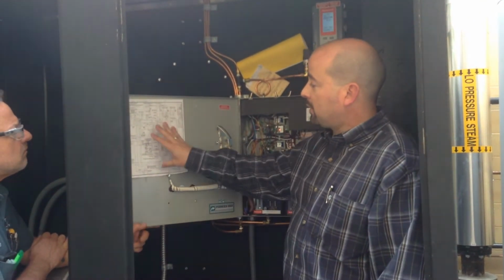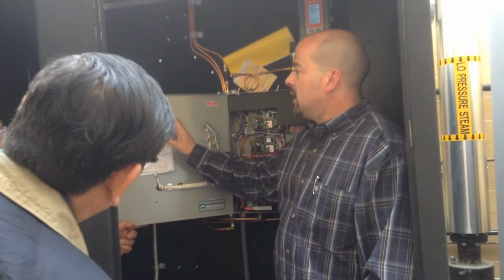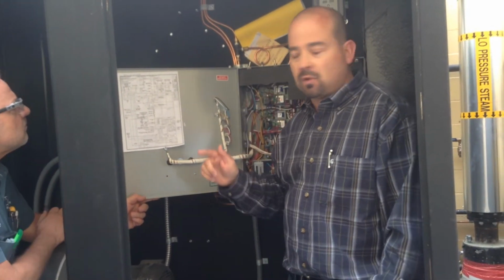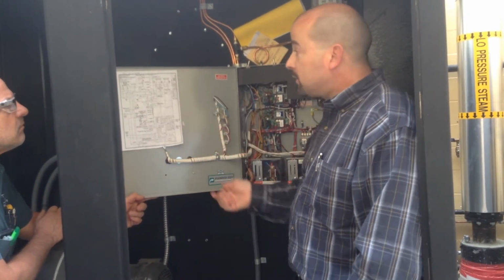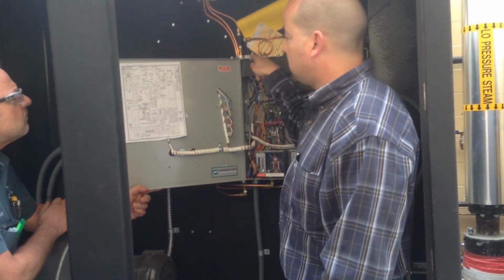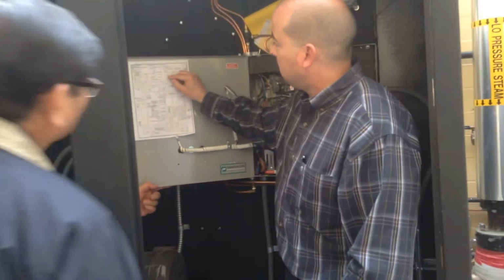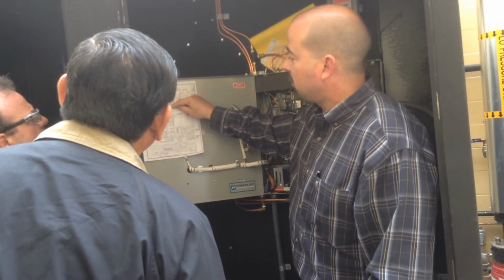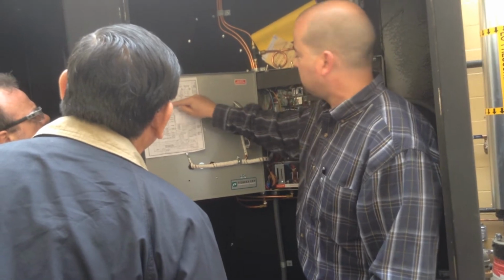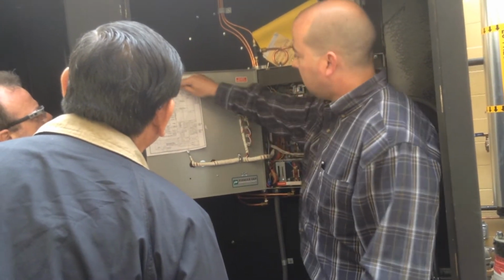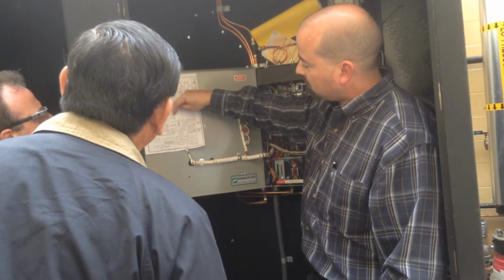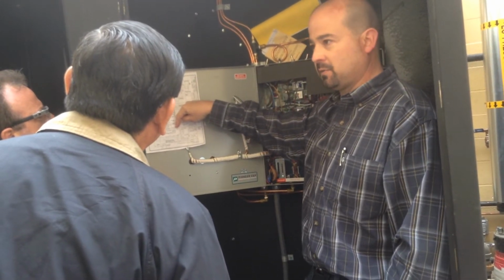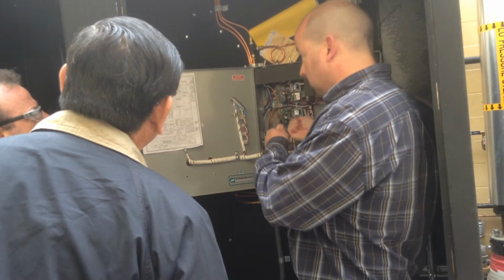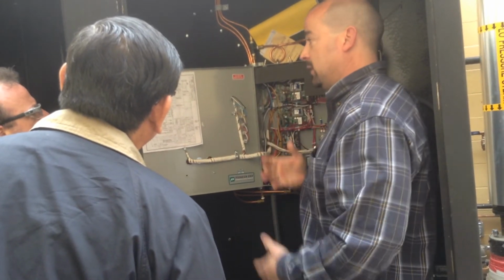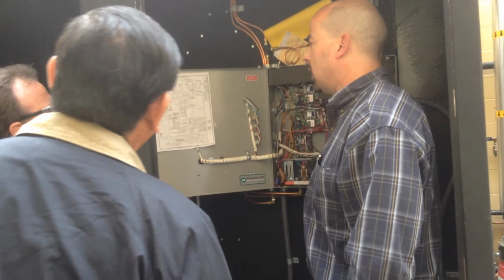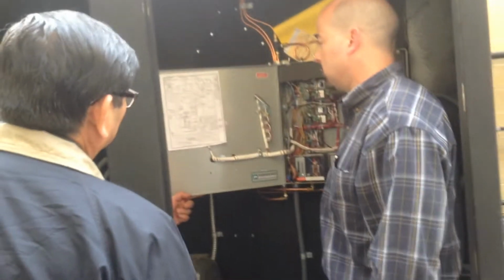One thing I want to point out about Parker Boiler's wiring diagram, which is really nice, is everything is from top to bottom. So if you're troubleshooting and you don't know what's going on, start at the switch. Okay? So you got your main burner switch, and then just work your way down. And it tells you, this depicts this control, this depicts this control, and it literally goes all the way down straight through a series of switches until it gets to the flame safeguard system. So you can literally just go boom, boom, boom, boom until you find the break. So it's a really intuitive and easy wiring ladder diagram to follow to figure out where the problem is.